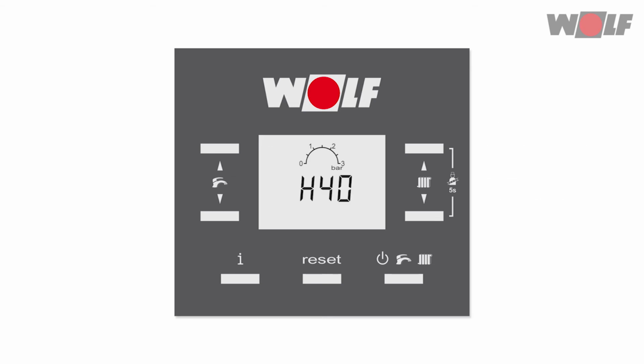Parameter H40. The condensing boiler is matched to the heating system by selecting from 3 pre-configured system configurations under parameter H40. This parameter influences the function of the internal appliance pump. Parameter H51. The domestic hot water configuration is used to set the type of domestic hot water heating. If the configuration is modified, all parameters are returned to factory settings except H12 and H40. 1. Combi mode. 2. Combi mode and solar integration. 3. Cylinder operation. 4. Heating mode only, no domestic hot water.